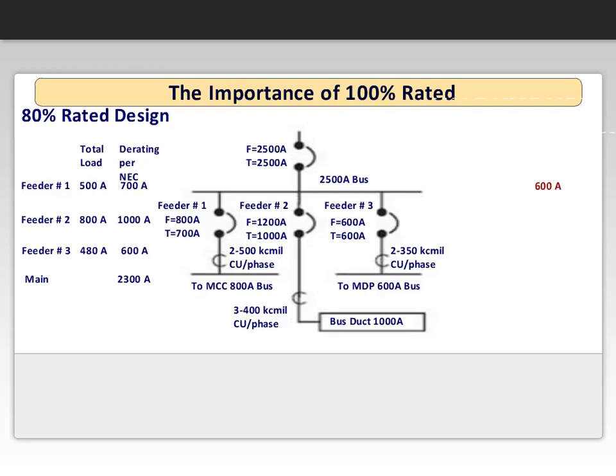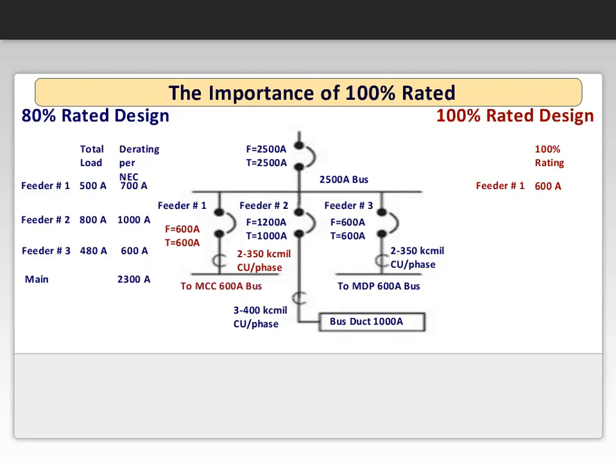Here's what occurs if 100% rated breakers are used. Feeder number 1 now becomes a 600 amp instead of an 800 amp. The cable size is reduced to two 350 kcmil copper per phase. The MCC bus can now be sized for 600 amps instead of 800 amps. Feeder number 2 changes to 800 amp frame instead of a 1200 amp frame.